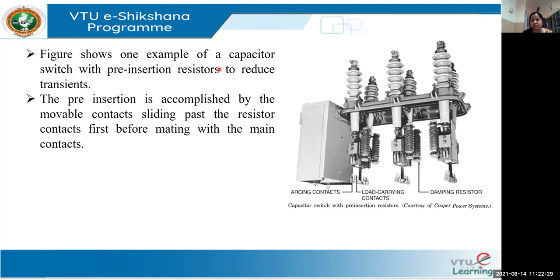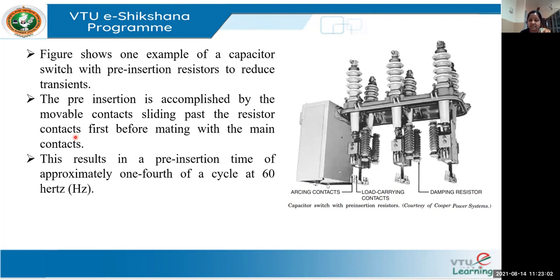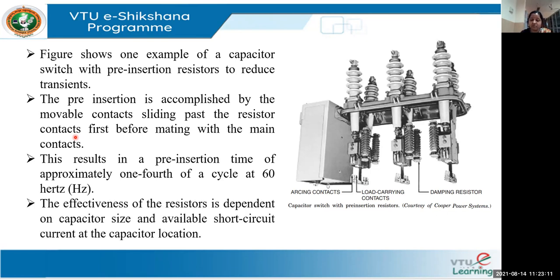This figure shows one example of a capacitor switch with pre-insertion resistors to reduce transients. The pre-insertion is accomplished by movable contacts sliding past the resistor contacts first before mating with the main contacts. This results in a pre-insertion time of approximately one-quarter of a cycle, which holds good for 60 Hz. The effectiveness of the resistors depends on the size of the capacitor being used and on the short-circuit current value at the point of capacitor location.